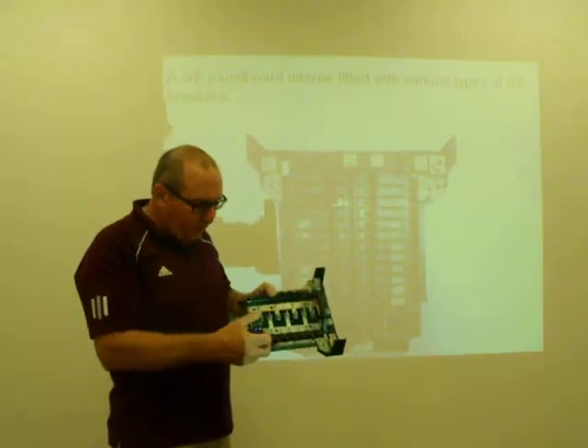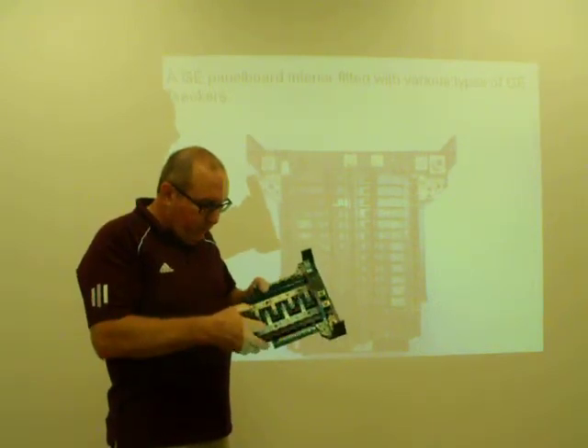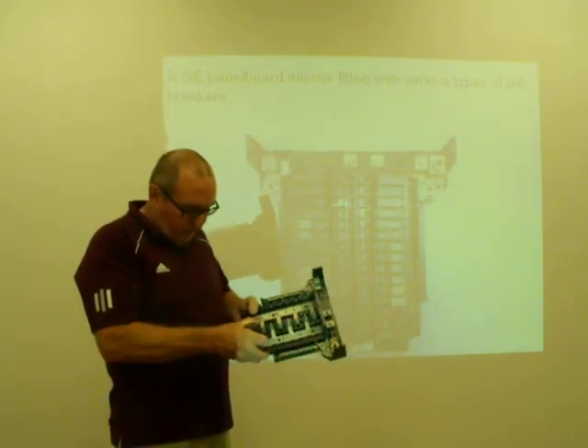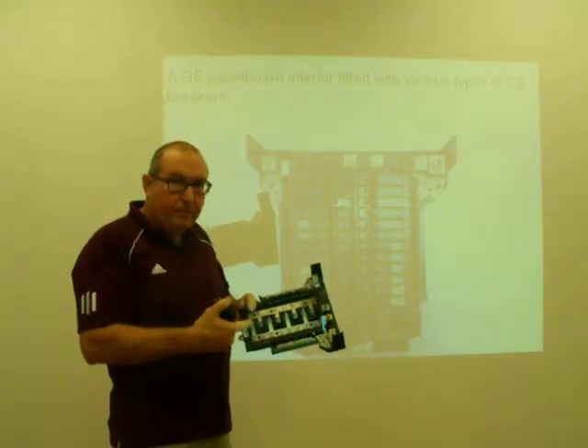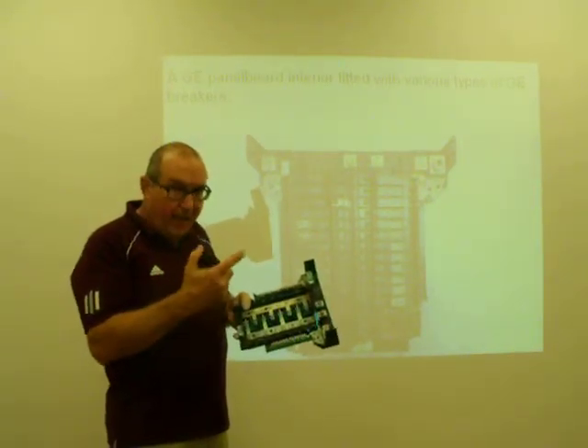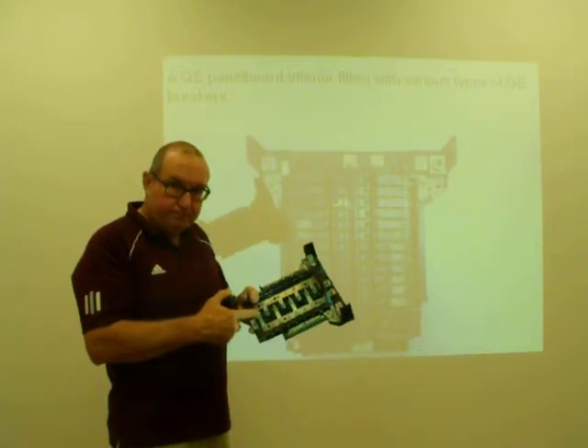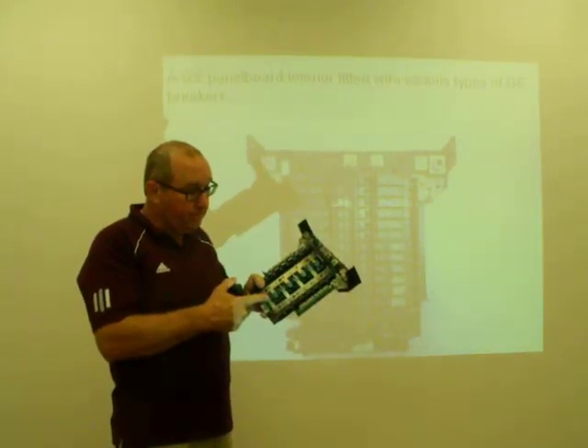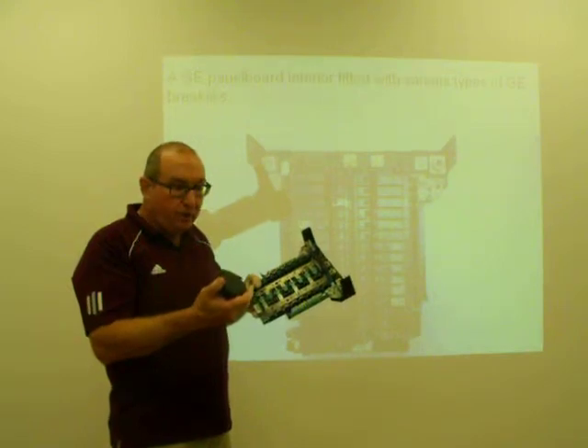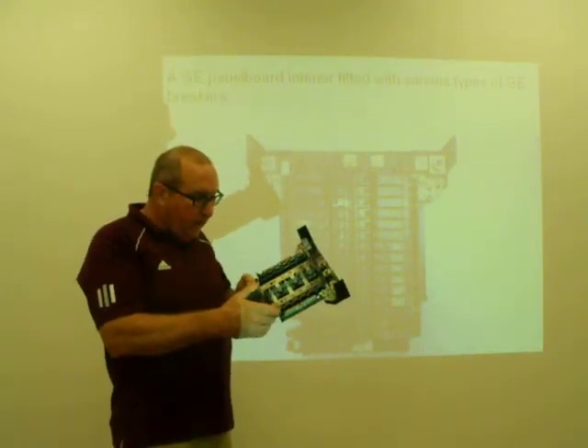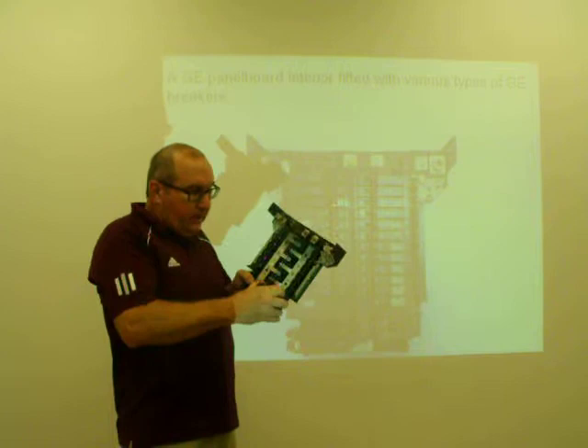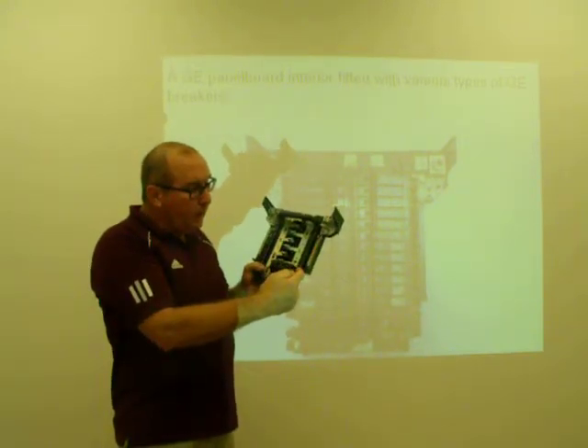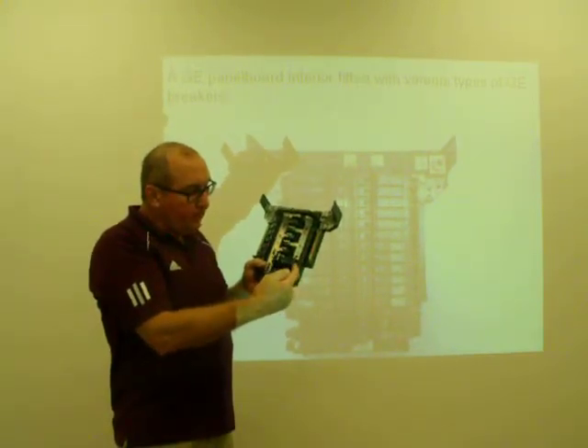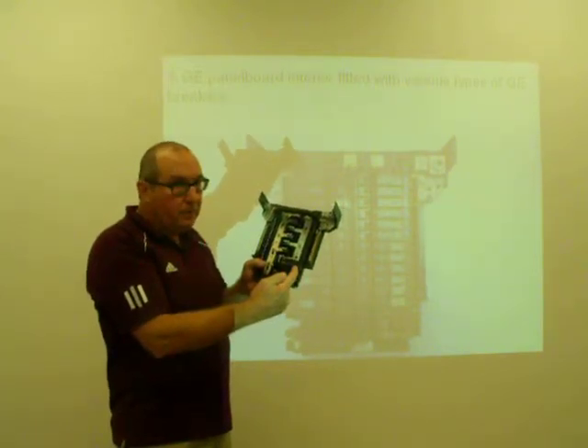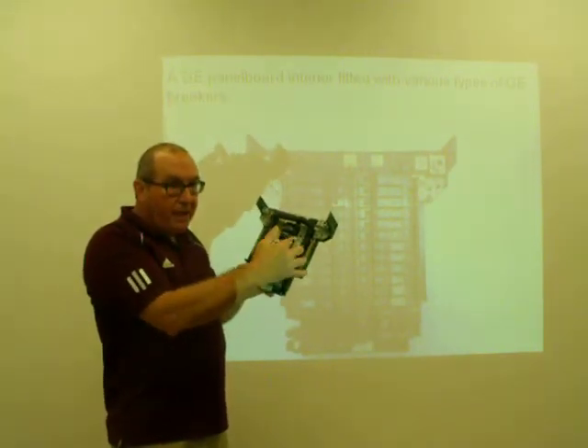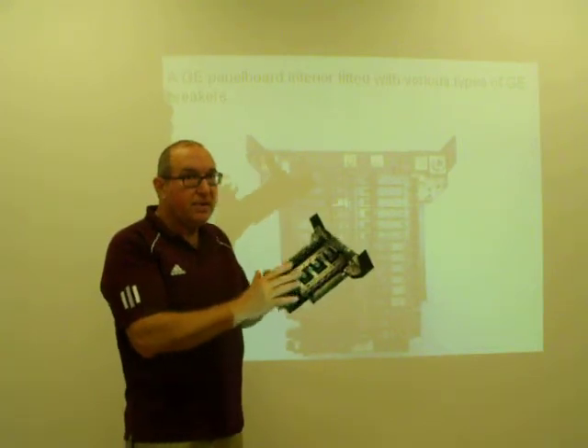So if you could install it in the wrong space, it wouldn't work. So if I try to put this breaker in a space here that's meant for 2 twins, I would be on the same bus. Both halves of this breaker would essentially be on the B bus. And that wouldn't do me any good as far as my 240-volt equipment. So I have to install it in between, and then it will fit. And then I'm on one pole on the top screw and I'm terminal, and I'm on the other pole on the bottom terminal. So even within this panel board using a GE breaker, there are limitations on where that breaker can be installed.